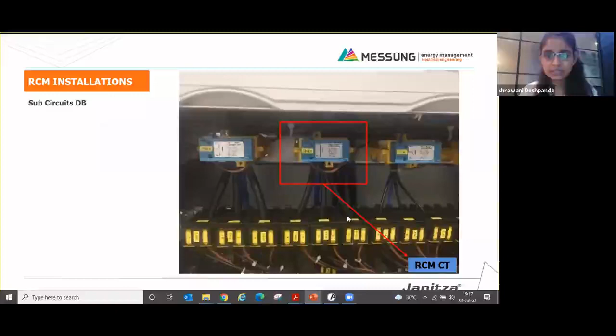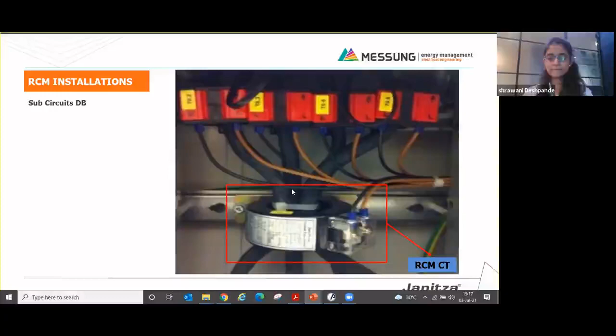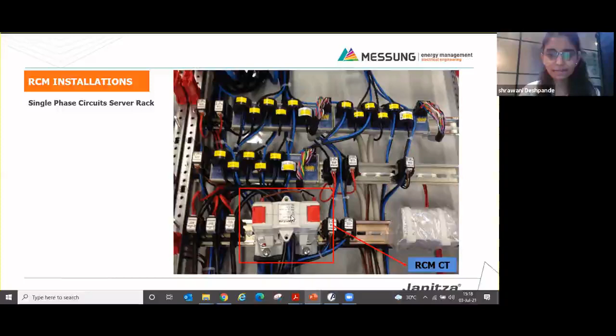This is again a sub-distribution board. In this is the RCM CT through which R, Y, B, that is the 3-phase conductors, are passing. Now this is the server rack. Here you can see one module, which is the UMG 20 CM. This is used for normal operating current measurement, and this is the RCM CT which is put for the server rack.